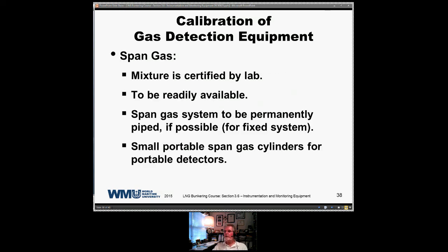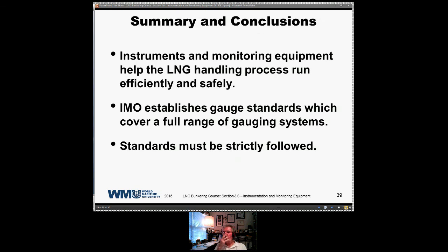Span gas, okay, I did touch on that a little bit. It's a mixture that's certified by a lab, has to be readily available, and has to be permanently piped if possible for fixed gas detection. Span gas to test it permanently. For your portable systems, you have a small span gas bottle that you use for your portable detector. Instruments and monitoring equipment help the LNG handling process run efficiently and safely.